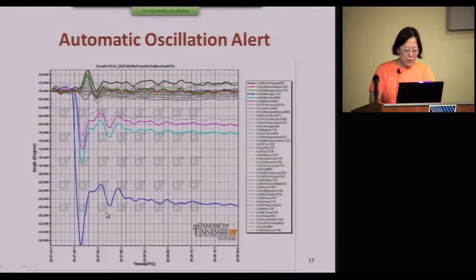This one gives a good picture of where the groupings are. This is EI. Looking at the vertical axis, this shows which units are reporting, because not everyone reports all the time. Typically PMUs report maybe half the time, but in this case we usually get more than 80% reporting data. They can stop reporting for all kinds of reasons, GPS being one of them, not because of snooping but because of weather. This clearly shows three clusters. You could further classify this, but it's probably not worth it because the magnitude gets so low — that's one group, another group, and a third group in terms of mode shape.